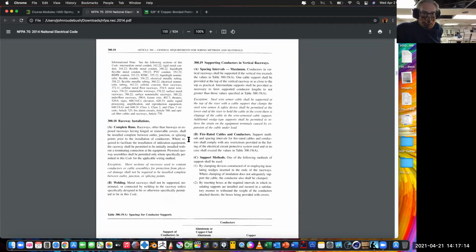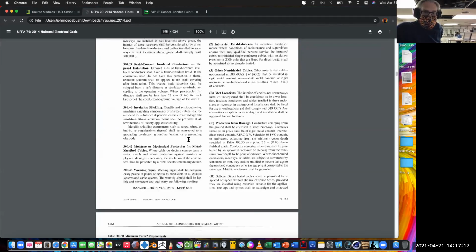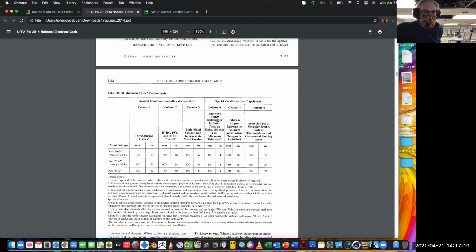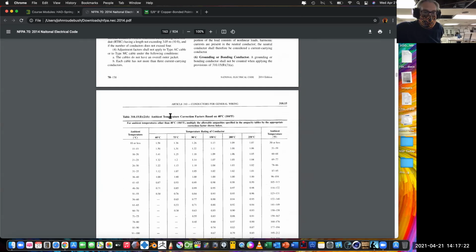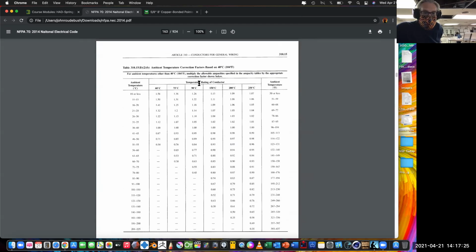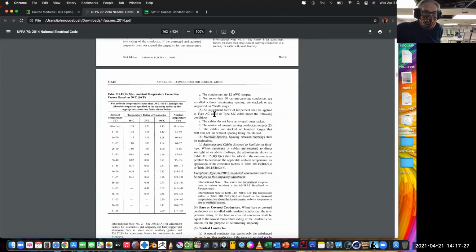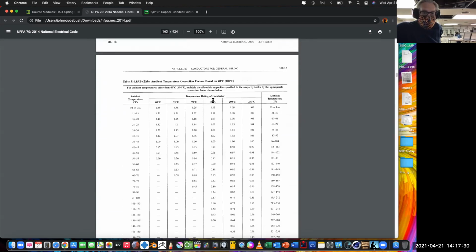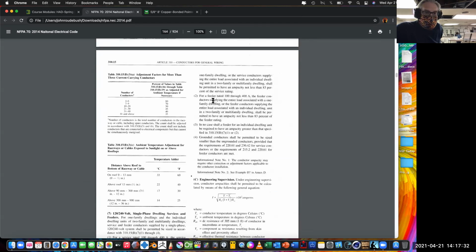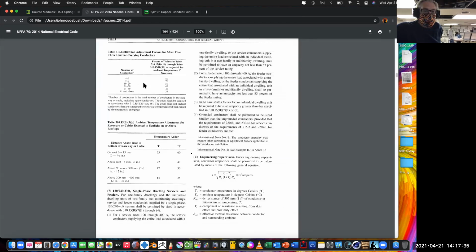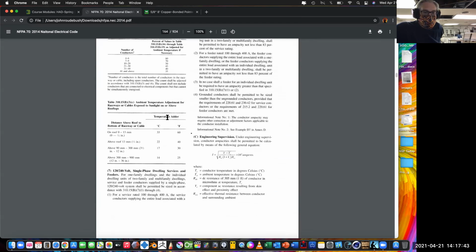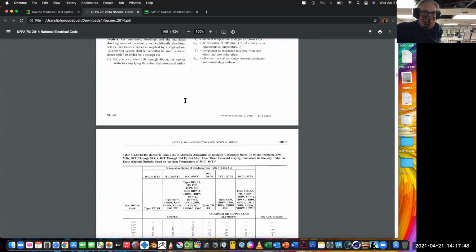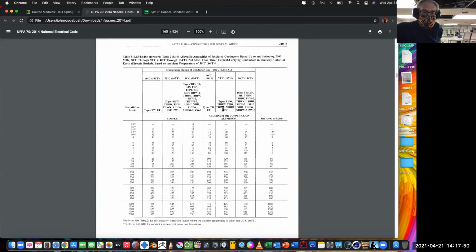Now we're going to run through this and find the table we're looking for. This is 300, we need to find 310.15(B), not this one, not that one, that's one we use though, that's our ambient temperature one. There's our number of conductors and adjustment factors for more than 3 current-carrying conductors per conduit fill. There we have our roof adder right there, we've used those already. And here we are in the chart we want to look at.